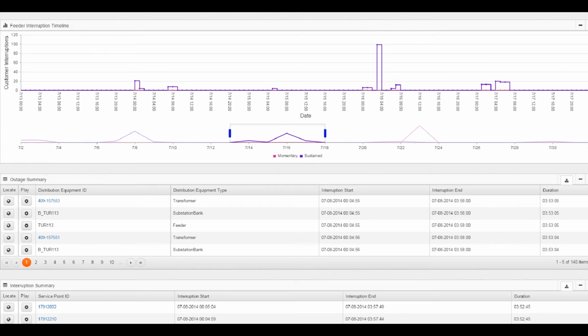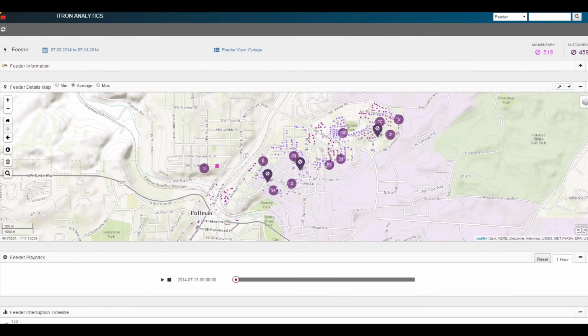In the feeder detail view, the engineer can review a time series playback of the outage as it occurs, or similarly for restoration events. In this example, service points are highlighted as the power outage notifications are received. With 1 second granularity, the operator can see exactly when the notifications were recorded at each meter. Analysts can choose playback intervals from 1 second to 1 hour for this data. A line graph provides a different view of the same information, showing the number of customers interrupted at any point in time down to the second.